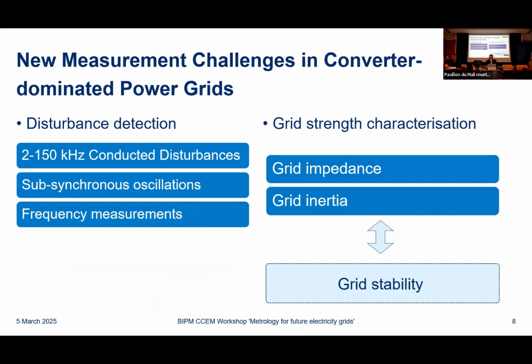So just to summarize the picture, there are new disturbances, and network operators need to be able to measure, characterize and monitor them to make sure the existing level doesn't surpass the compliance limits. So we've got the high frequency new disturbances, the subsynchronous oscillations, but also frequency measurements are becoming a lot more important because of this reduced inertia. We can get worse and more frequency deviations depending on what's happening in the grid. On the other side, we also need to characterize this grid strength. So what is the impact of such disturbances potentially going to be in the grid? I'm very conscious that I'm crossing over a bit into another talk.